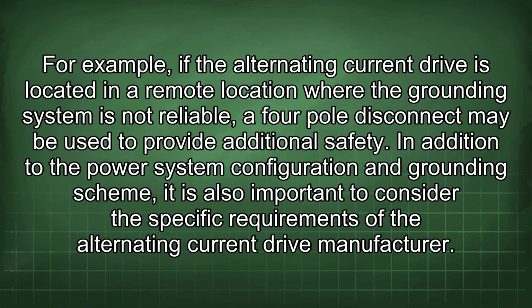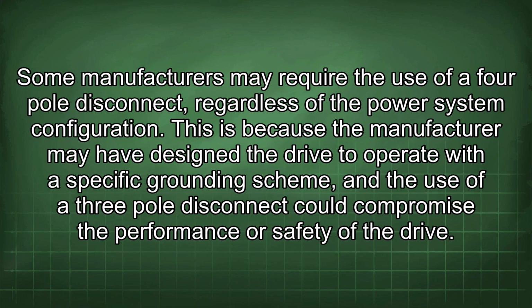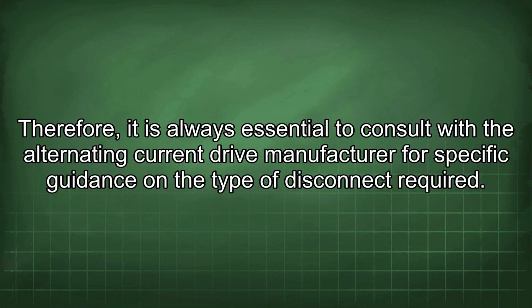In addition to the power system configuration and grounding scheme, it is also important to consider the specific requirements of the alternating current drive manufacturer. Some manufacturers may require the use of a four-pole disconnect, regardless of the power system configuration. This is because the manufacturer may have designed the drive to operate with a specific grounding scheme, and the use of a three-pole disconnect could compromise the performance or safety of the drive. Therefore, it is always essential to consult with the alternating current drive manufacturer for specific guidance on the type of disconnect required.